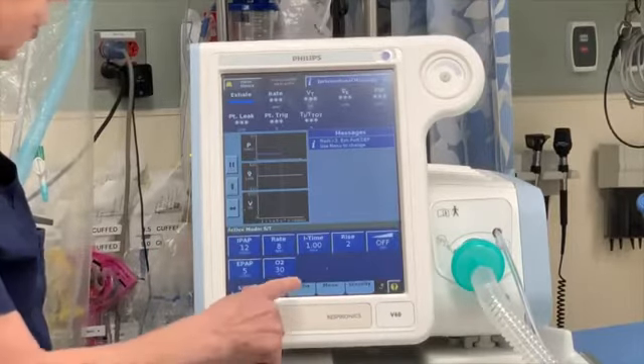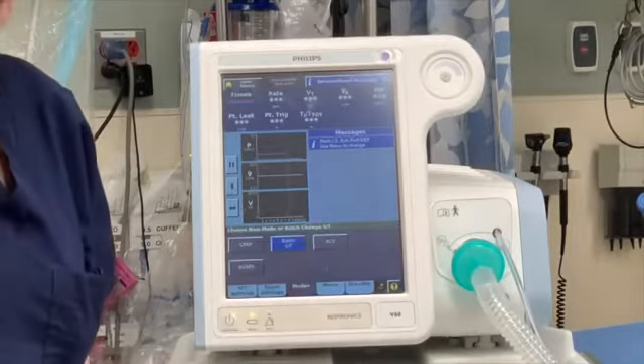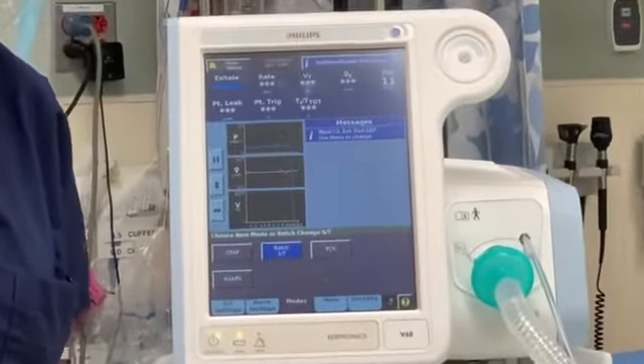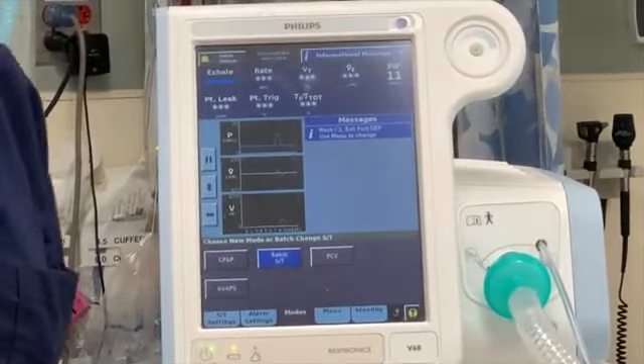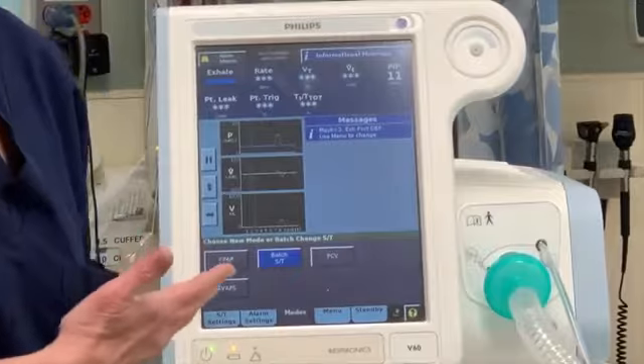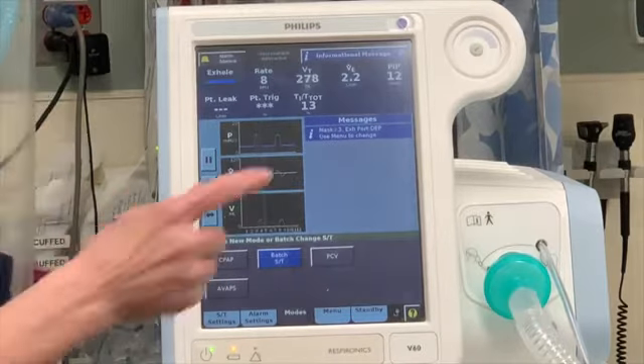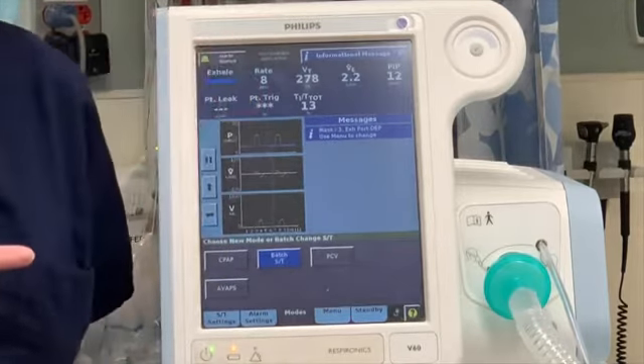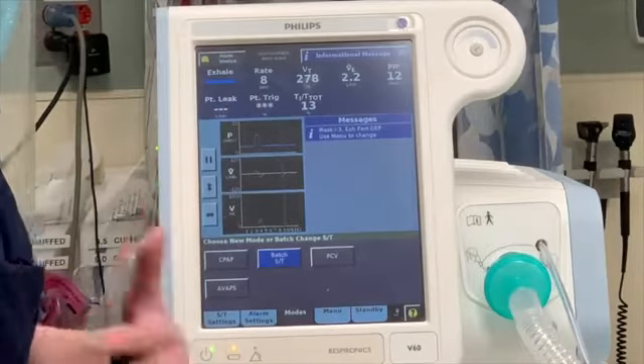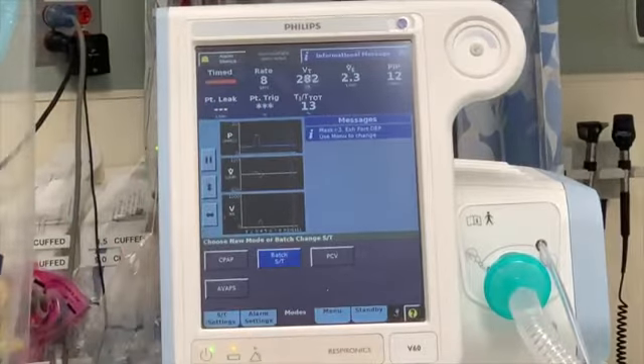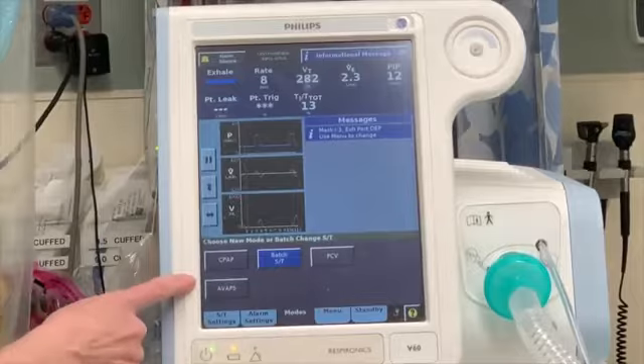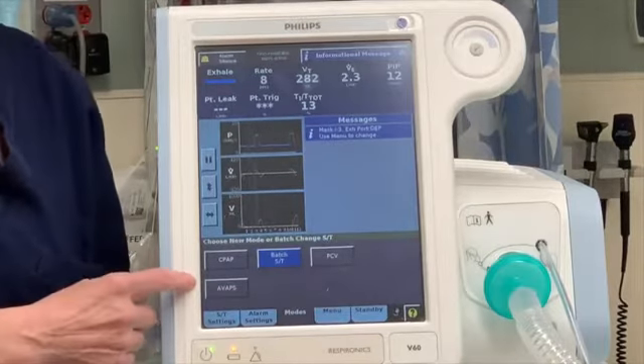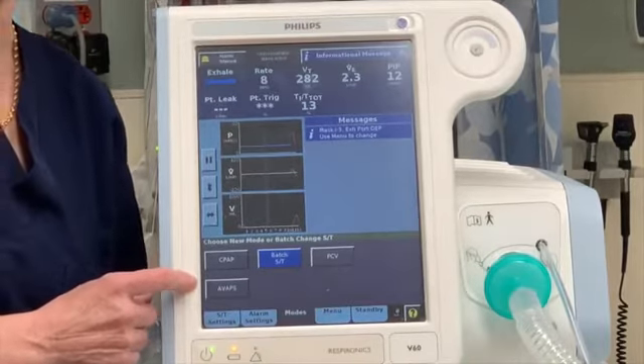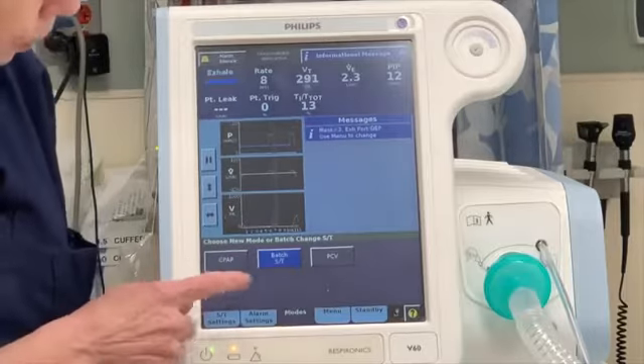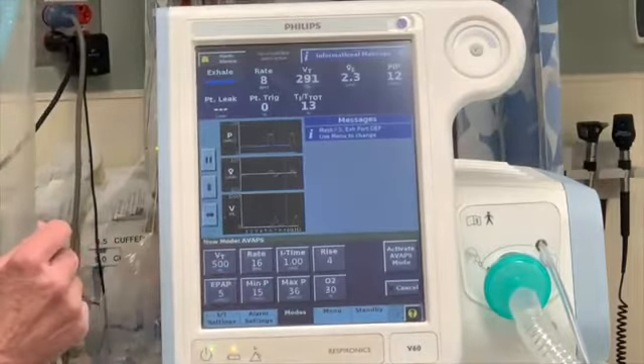So the first thing you need to do is to go into mode. You need to tell the machine that you're not going to use it as Bi-pap. You want to use it as a ventilator. There's several different settings you can use as a ventilator in these machines. I'm going to show you one. I'd encourage you to contact your representative for the machine you're using, and they can go over all the different parameters and how to do it. So the setting I'm going to use is something called AVAPS. That stands for Average Volume Assured Pressure Support. And that's just one way to do the ventilator. Now you have to activate it for it to work, so now it's activated.